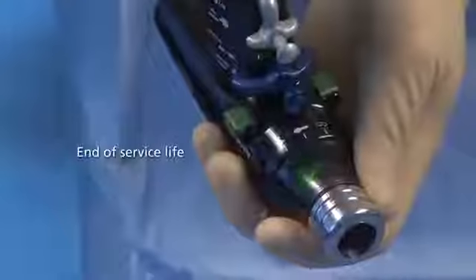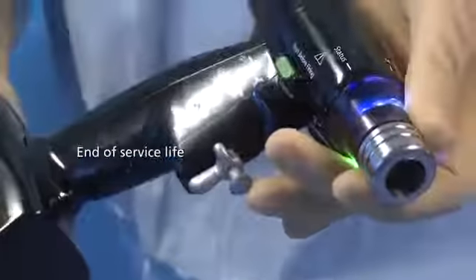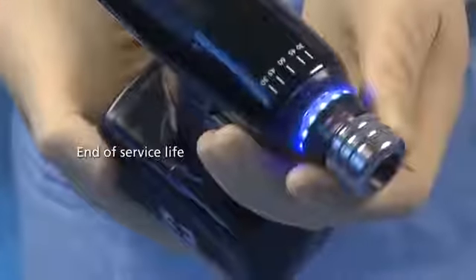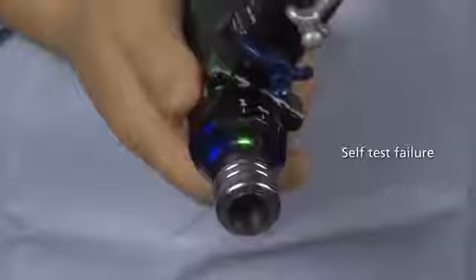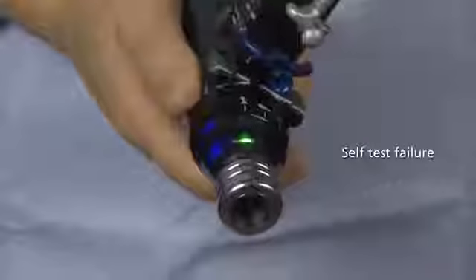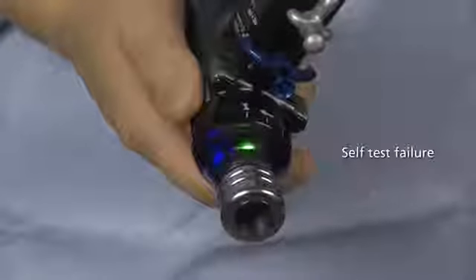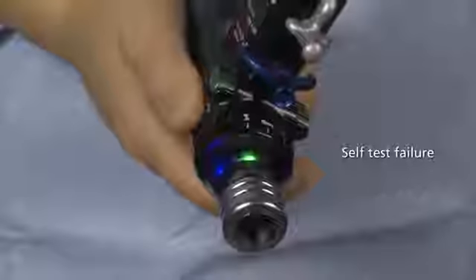If the powered handle has reached the end of its service life, the handle status indicator light will remain flashing green, the general status indicator lights will turn solid blue, and the 5 white firing progress indicator lights will flash white. A self-test failure, on the other hand, is indicated by a flashing green handle status indicator light and solid blue general status indicator lights. The white firing progress indicator lights will not be illuminated in the event of a self-test failure.